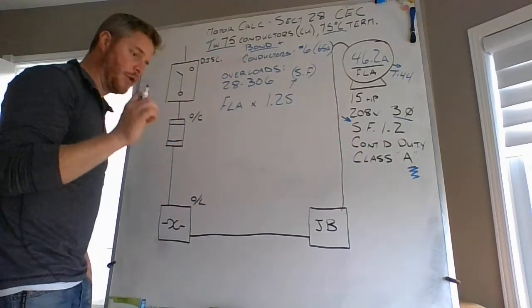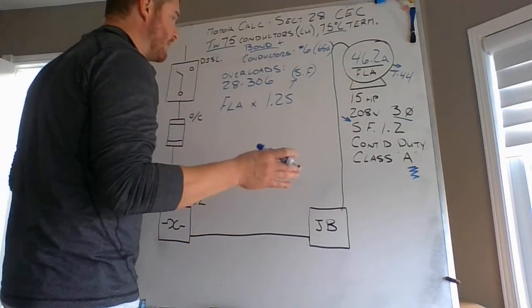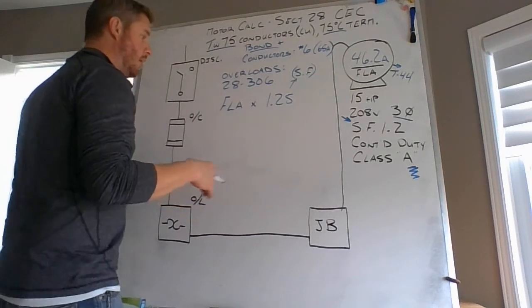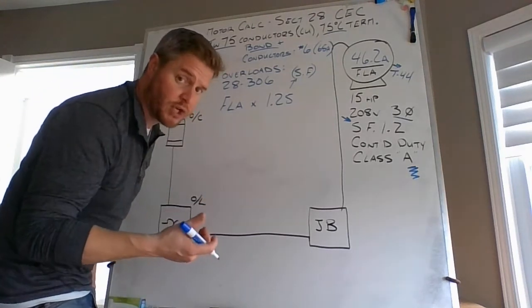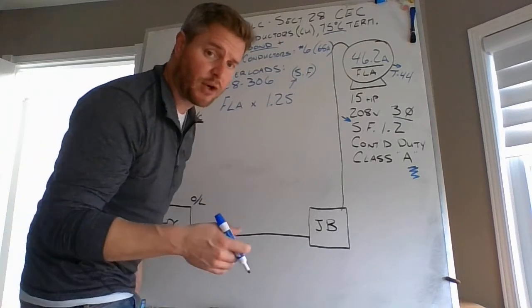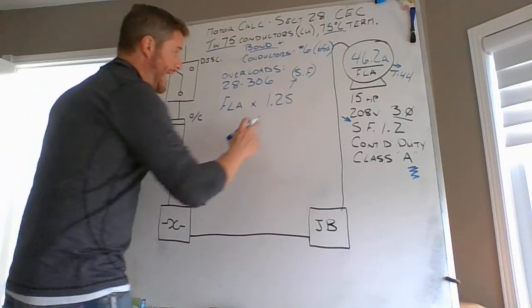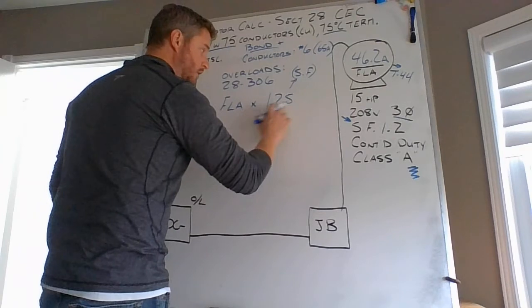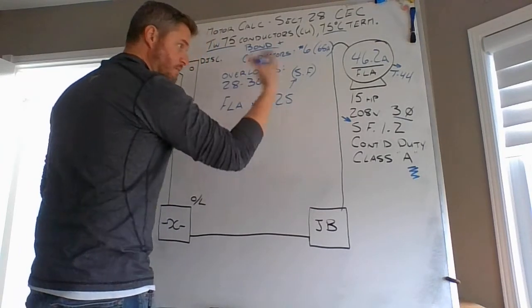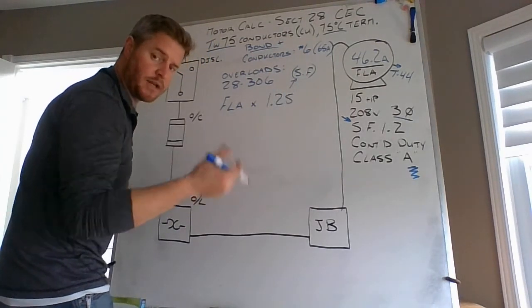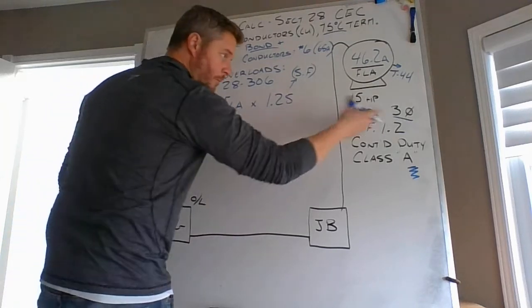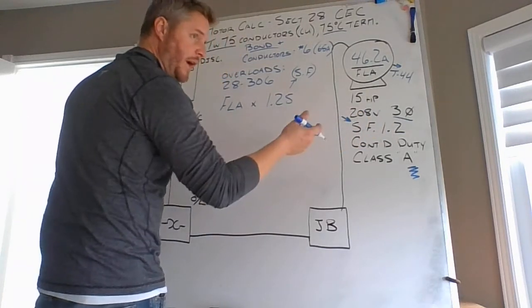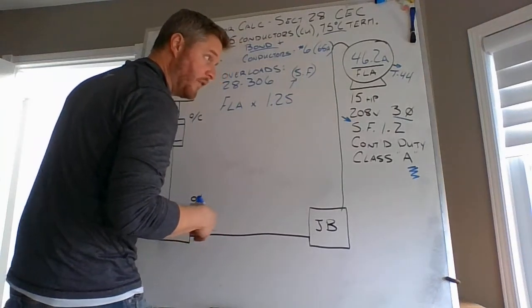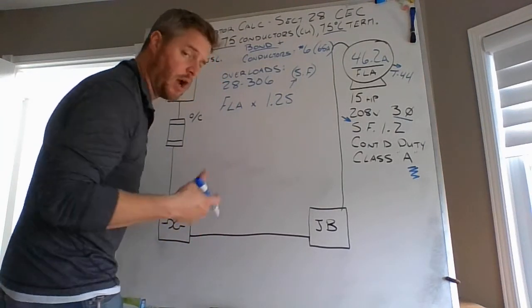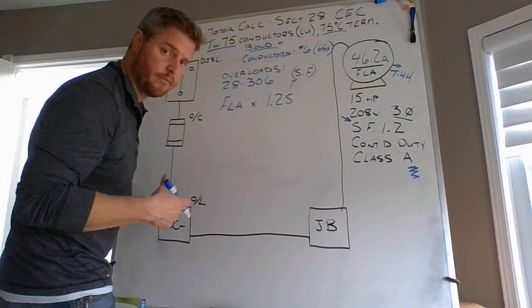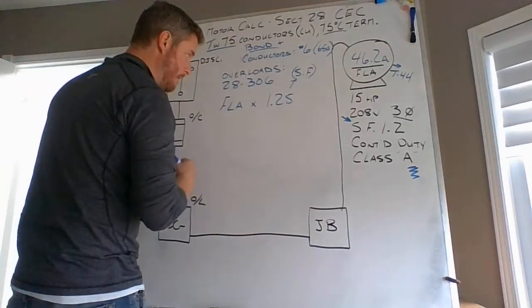If that nameplate had no marking for that service factor, or in the question that I might give you, your service factor was not marked, then you cannot use the 1.25 multiplier that you see here in this specific equation. It doesn't exist. There is no marked service factor, or the service factor is less than 1.15. In that case, it's a very untrustworthy motor. And I'll show you those means in a minute.